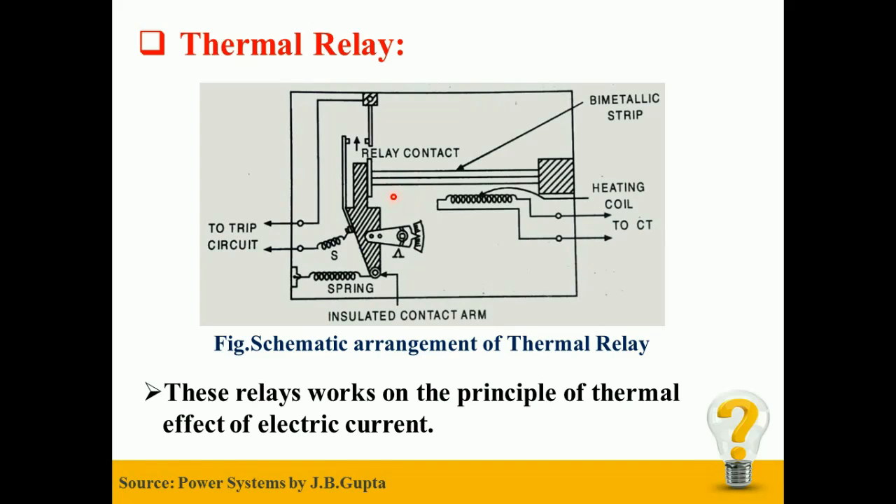Under normal working conditions, the strip remains straight. But under the action of fault current, heavy current comes from the CT side which flows through the heating coil. Therefore the heating coil gets heated up and radiates its heat towards the bimetallic strip. The strip is heated and bends, therefore the tension of the spring is released, and the relay contacts are closed which energizes the trip circuit.